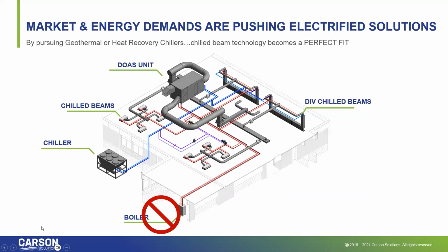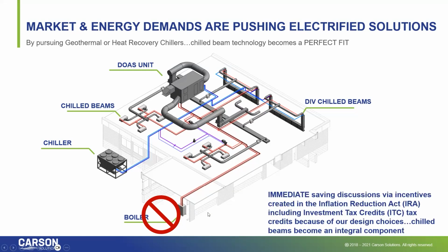Now, if we take a look at what's on the screen, we have that same building schematic. And what if we want to pursue an electrified solution, either heat recovery chiller or geothermal, and eliminate that fossil fuel burning boiler? Now, if we go down that path, we immediately check the box for qualification of the Inflation Reduction Act, 30% top line tax credit plus modified accelerated depreciation as well.